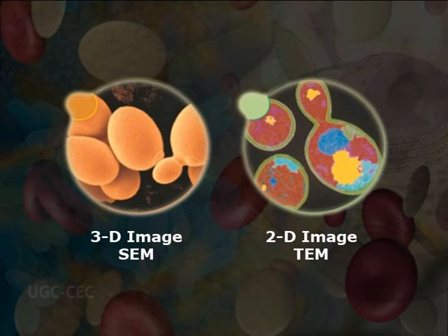In terms of magnification and resolution, TEM has an advantage compared to SEM. The resolution of TEM is 0.5 angstrom, while SEM has 0.4 nanometer. However, SEM images have a better depth of field compared to TEM images. Another point of difference is the sample thickness, staining procedure and preparation. The sample in TEM is cut thinner in contrast to the SEM sample.